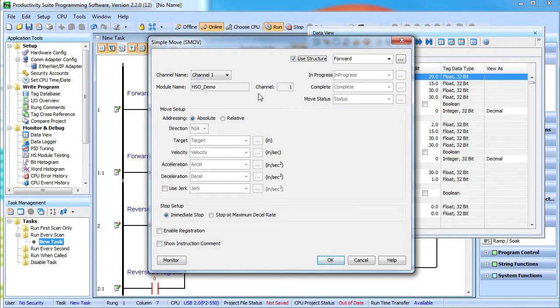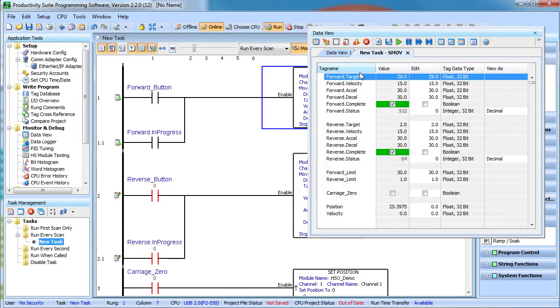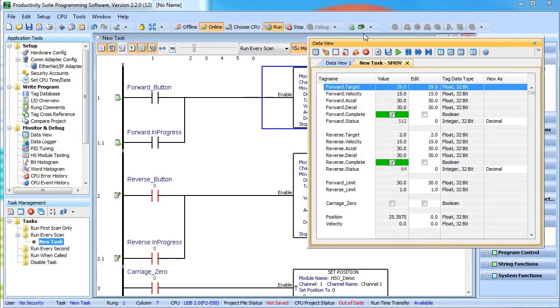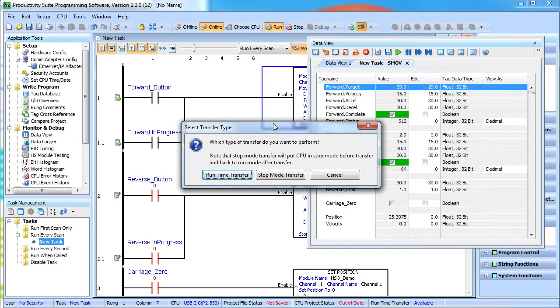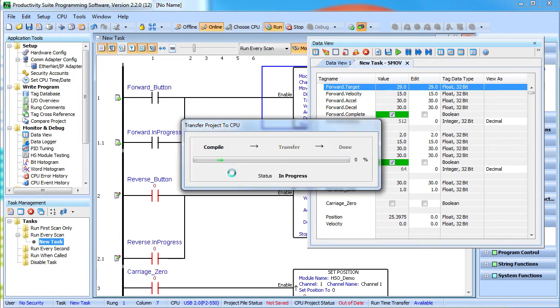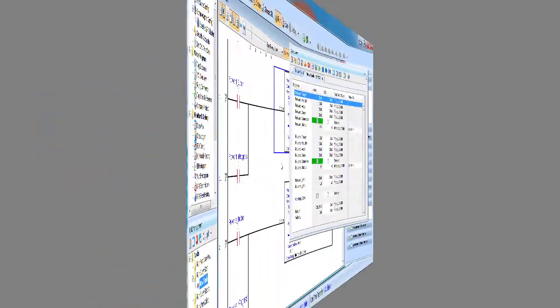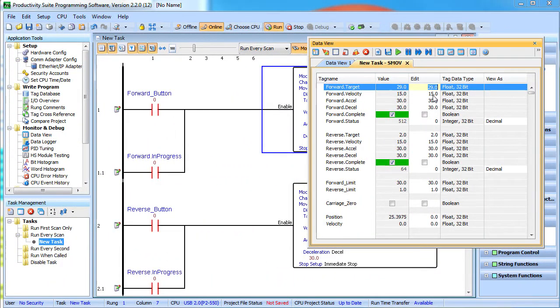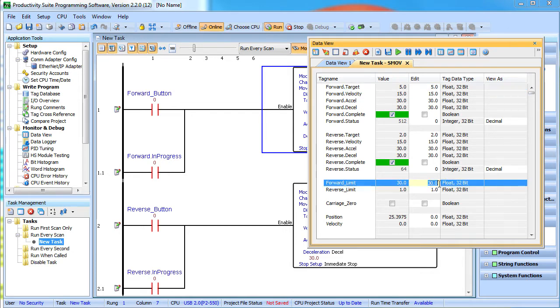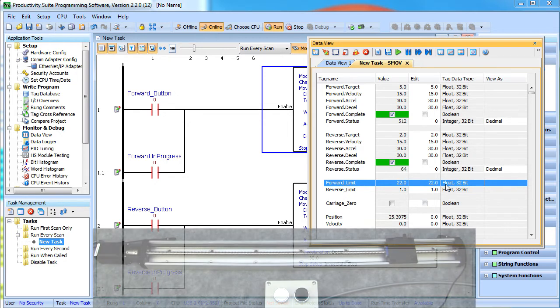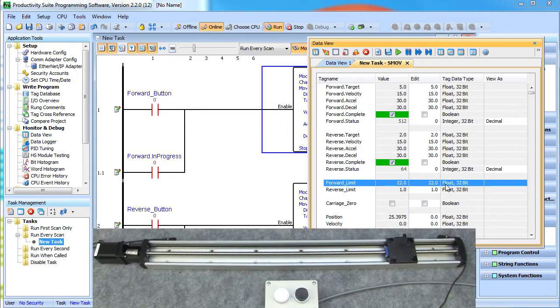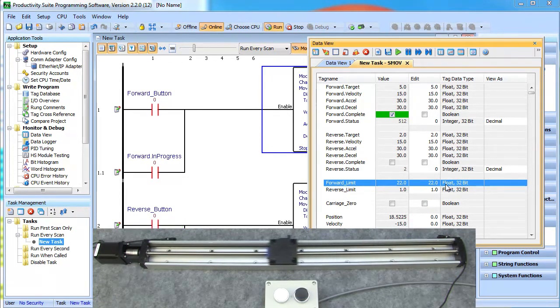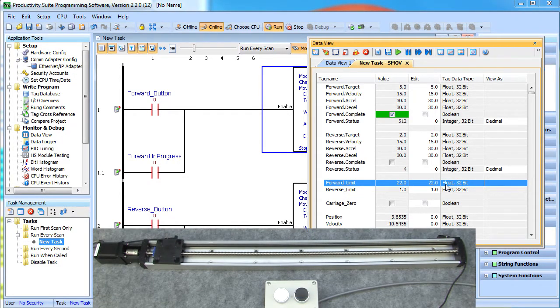Now while we are here, let's enable this relative move in the forward direction only and send that down to the controller and see what it does. Let's modify the forward target distance to be 5 inches. And while we are at it, we will get the position limit back in bounds from that change we made in the last example. The reverse direction is still absolute, so let's send the carriage back to the absolute 2 inch mark.